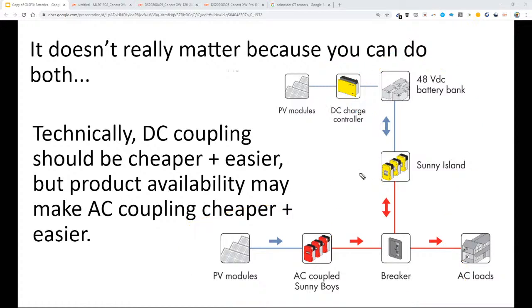The big difference between AC and DC coupling: with AC coupling you're actually buying two inverters, which might cost a bit more, but not always—and you get the combined power output of both systems when the solar array is on. With DC coupling, you don't get that advantage of having two inverters on site. So you can actually get more power out of an AC-coupled system than a DC-coupled one for about the same price. DC coupling wins the theoretical technical argument for reasons we don't have time to discuss, but pragmatically AC coupling is winning because there are more manufacturers of inverter products than charge controller products.